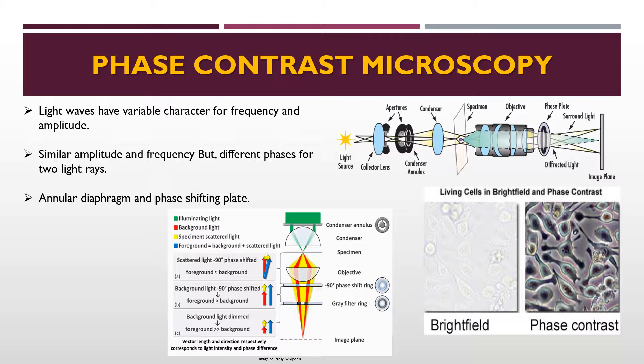In phase contrast microscopy, light passing from one object into another of a slightly different refractive index or thickness undergoes a change in phase. Light waves have variable character for frequency and amplitude; when two light rays have similar amplitude and frequency but different phases, this microscope is used to image the specimen. It is used to visualize unstained living cells — most staining processes kill cells, but phase contrast enables visualization of living cells. In a phase contrast microscope, differences in phase are translated into variations in brightness, making them detectable by eye. A phase contrast microscope is a compound microscope fitted with a phase contrast condenser and phase contrast objective.